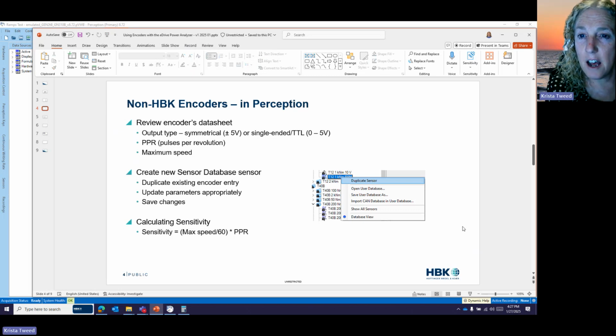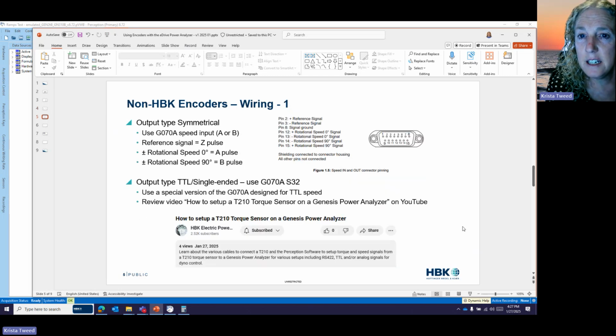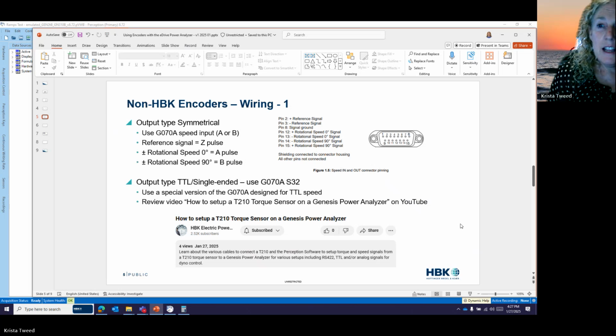All right, so that's how we create a new sensor for one that's not already in the sensor database. Now, what about wiring? This is where you've got to look at what type of output that encoder has. If it is a symmetrical type output, just like the HBK encoders, then you're still going to use that G70A torque adapter box and use either the speed input, either A or B side, it doesn't matter.